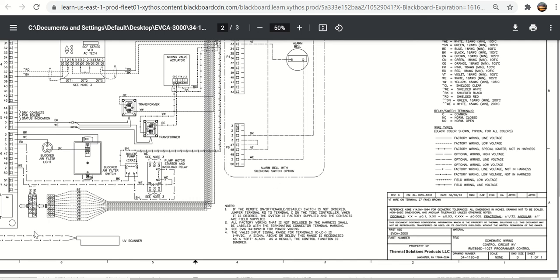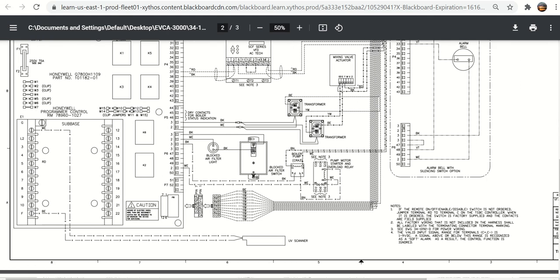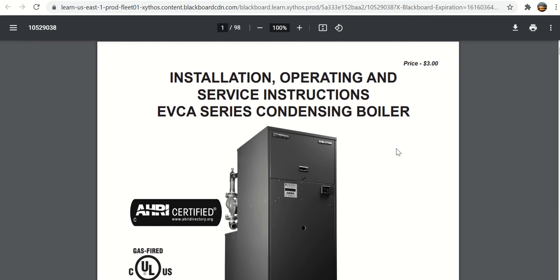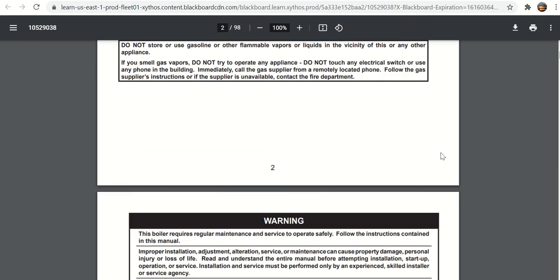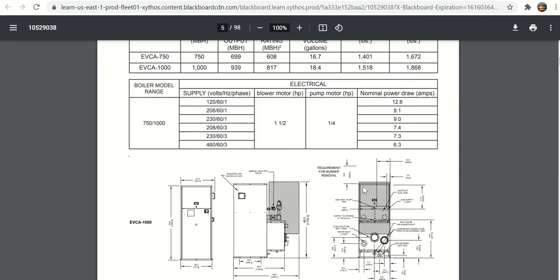Down here is the UV scanner. I think this is the one thing that's a little bit different. On most of the flame safeguards we talked about previous to this, we were doing flame rod, and this one actually uses an ultraviolet scanner. I want to take a quick look at the manual here, and I see how much time I got. I got plenty of time left.